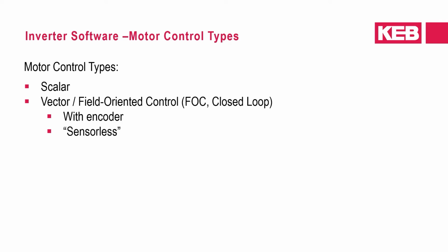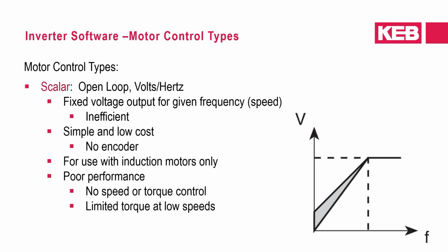These generally include scalar control and vector or field-oriented control with either encoder feedback or sensorless feedback. Scalar control is also known as open loop or volts per hertz. Here, the inverter outputs a fixed output voltage for a given frequency based on a volts-hertz curve. Since the output voltage is only determined by the speed command rather than the actual power requirements of the load, volts-hertz operation can be less efficient under partial loads. This type of motor control is generally pretty simple and low cost since a motor encoder is not needed. It also only applies to asynchronous motors since the rotor magnetization is induced, whereas synchronous motors need feedback in regards to the rotor position. And lastly, open loop tends to have relatively poor performance since there's no speed or torque control and there's limited torque available at low speeds.